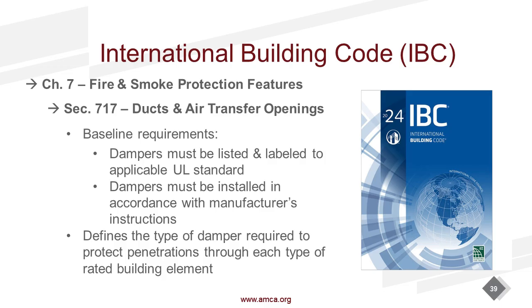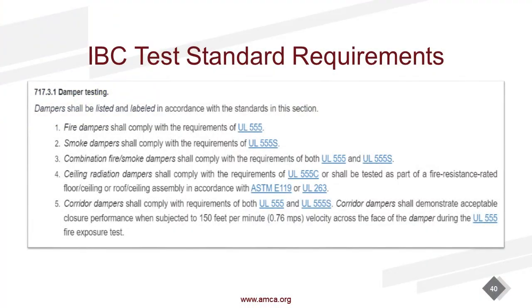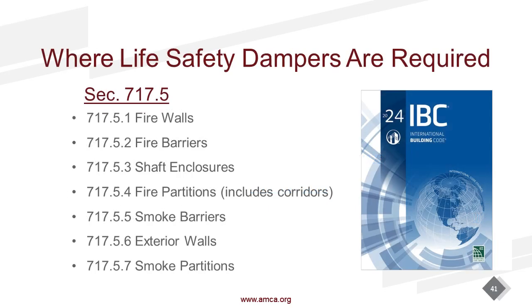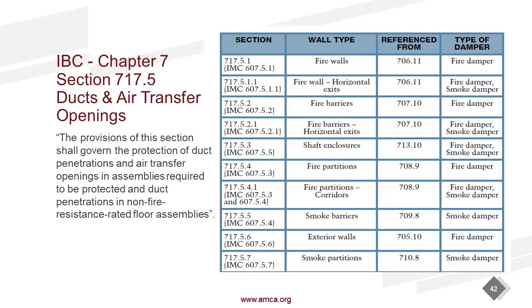So again, there's only a handful of installing contractors here. We don't like to point fingers at all. But a lot of the deficiencies we find with dampers is not in the construction, it's not in the materials, it's in the installation. Something was missed, something was assumed, or something wasn't done properly. So a lot of different things in the building code. I'm not going to go through all of them. Again, Chapter 7 has all the information you're going to need, where dampers are required. This presentation will have a little cheat sheet here. It's not an end-all, be-all, but it'll tell you the wall type, the code section that it's referenced from, and the type of protection that's required.